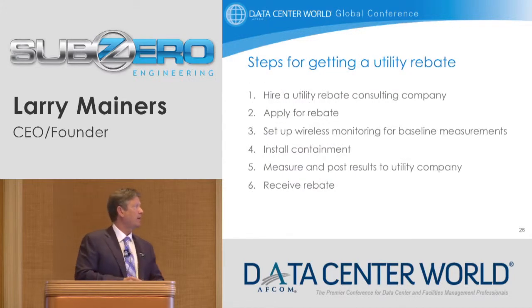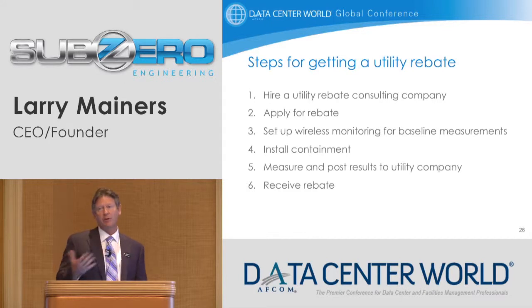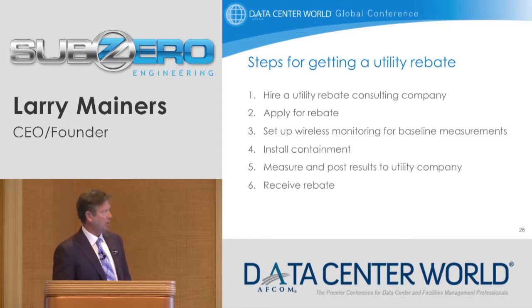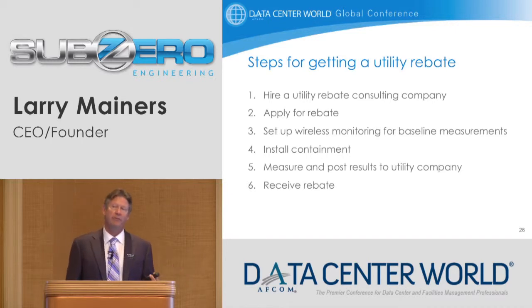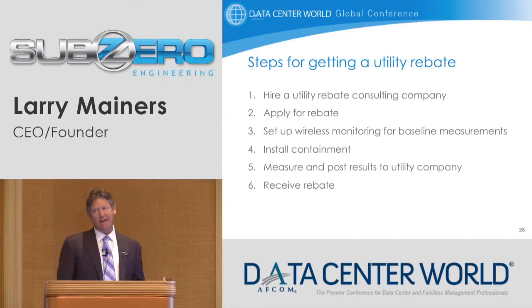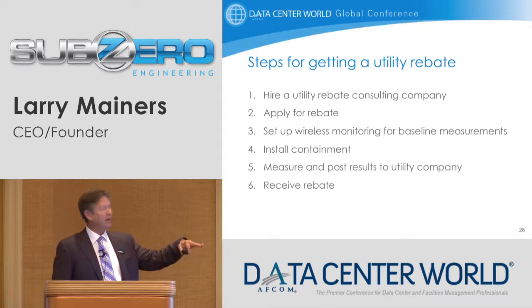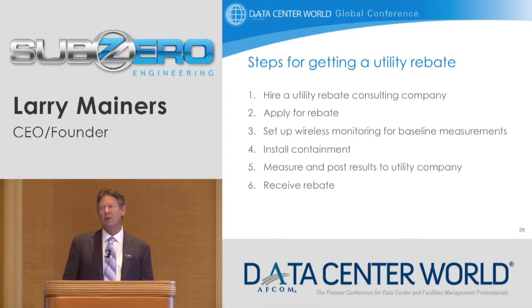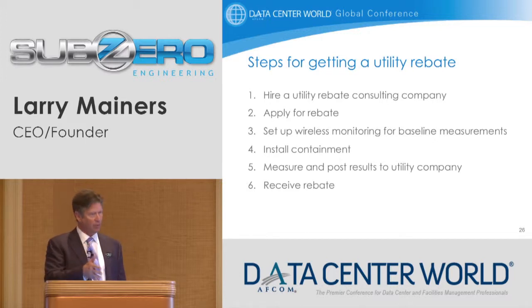In order to get a rebate, you have to deal with a utility company. If you can do that directly, fantastic; if not, there are consulting companies that can work with you. The application is made in advance, then monitoring takes place from an environmental point of view and also the consumption of power. Then the airflow management system is installed, the environment is monitored as set points are changed, and then you do a pre and post comparison of the energy used before and after the airflow management, which ends up with a rebate.